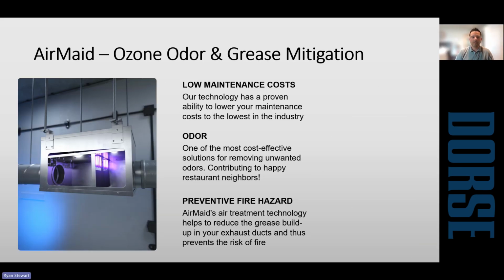Another option where maybe a full-on PCU isn't required by the jurisdiction, but there's concerns about odor or grease mitigation. They don't want to see grease on the louver of a building, or this would be another thing for retrofit, but it's using UV to produce ozone. It's very effective at reducing odors from grease-laden vapor. And it also does a good job of reducing the volume of grease in ductwork. The important thing with this is it needs time to react. So the longer the duct run, the more effective this approach is. The manufacturer recommends a minimum of a 3 second reaction time. But again, the longer the duct run, the better.